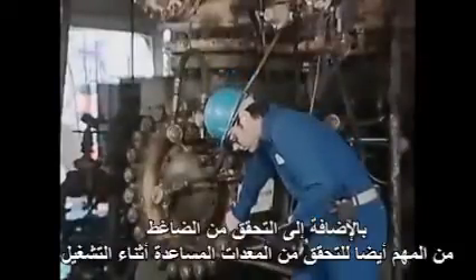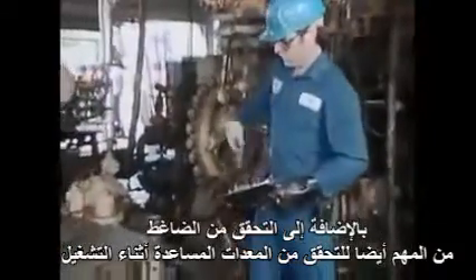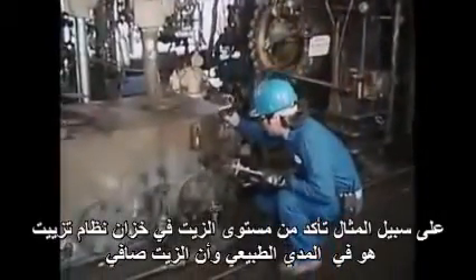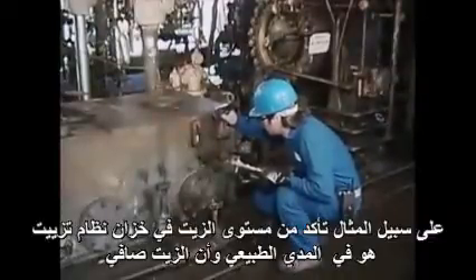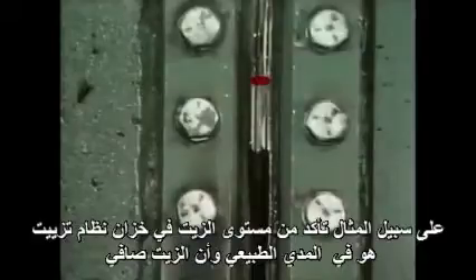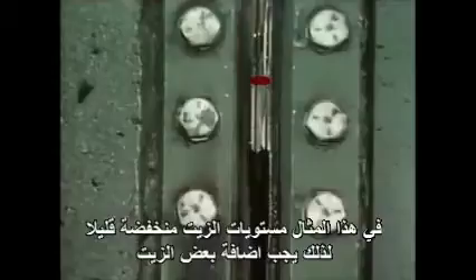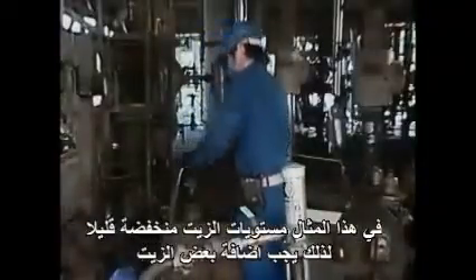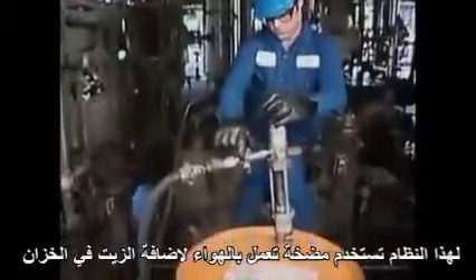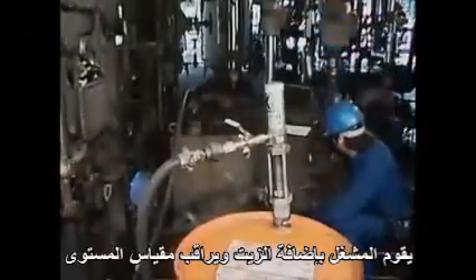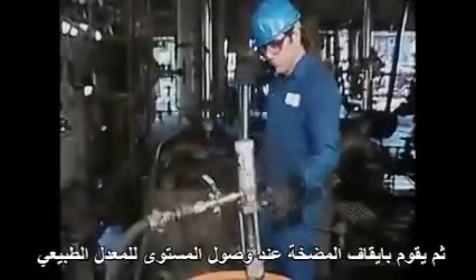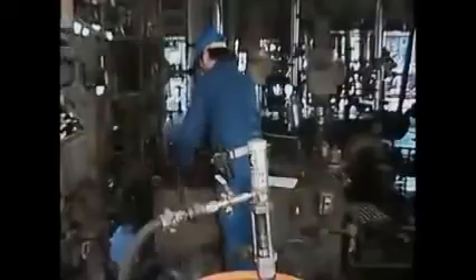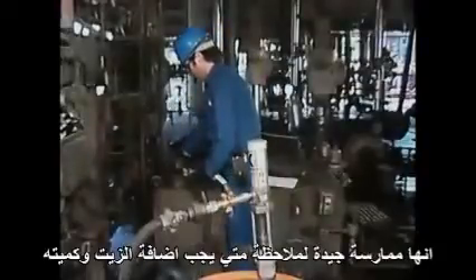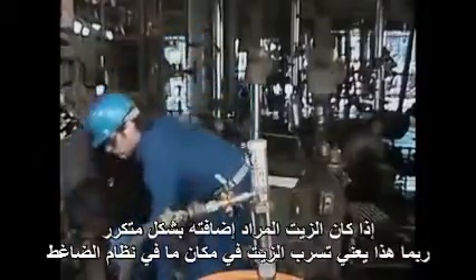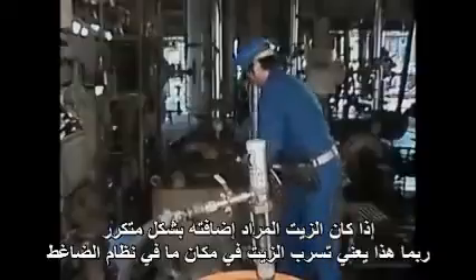In addition to checking the compressor, it's also important to check the compressor's auxiliaries during operation. For instance, make sure that the oil level in the lubrication system reservoir is within the normal range and that the oil is clear, not gritty or milky. In this example, the level's a little low, so some oil must be added. For this system, an air-powered pump is used to add oil to the reservoir. As the oil is added, the operator watches the level indication. He shuts the pump off when the level reaches the normal range. It's a good practice to note when oil is added and how much. If oil has to be added frequently, it probably means that an oil leak has developed somewhere in the compressor system.